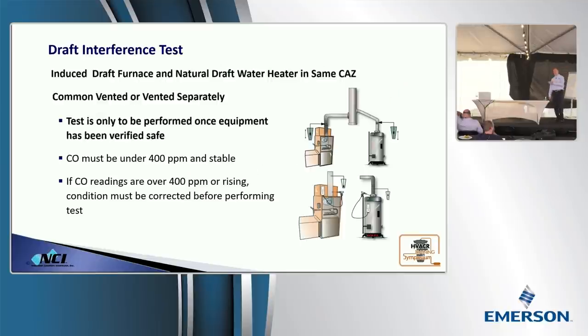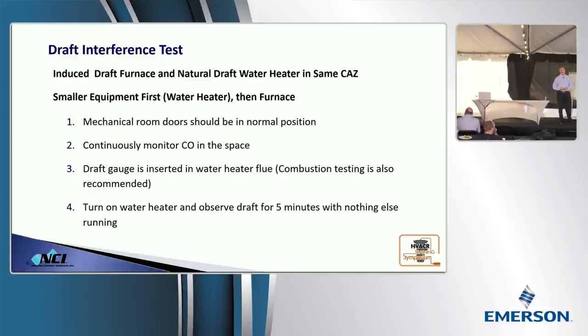So the first thing we need to do is see what's interfering with the equipment. This is where we do a draft interference test. Number one, the equipment has to be safe. So we kick the equipment on, we're running it, and we're making sure that it's stable. First thing we got to do, everything is in normal position. This is a lot harder to do than it sounds like. Think about that water heater. If you're testing a water heater that's in a closet, the door is normally in what position? It's closed, right? How do we normally test them? Open. Oh, you can't do that. Hey, there's test instruments that are Bluetooth that do that. They'll help you. You're always monitoring the space.